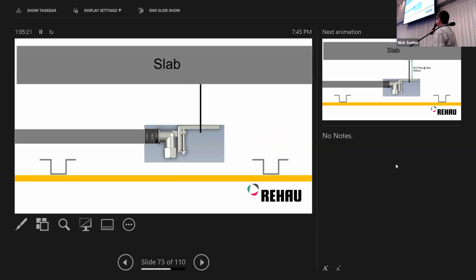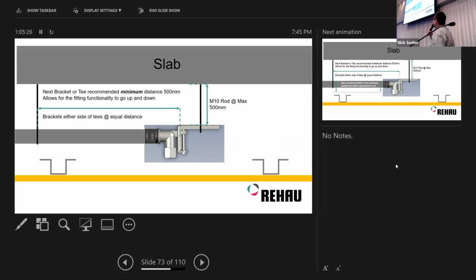And then when you've got a longer installation, that's where you utilise your M10 rod. For the next bracket, we want to ensure there is a certain distance away, a minimum of 500 millimeters, which is sitting about here. That gives you the flexibility, if that's fixed to the slab, to go up and down. If that next clip is sitting here, you're not going to be able to screw this up and down. So the next one over is at 500 millimeters.